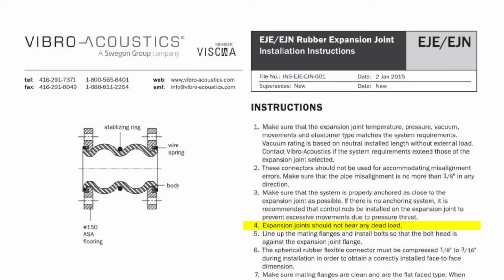Elastomeric expansion joints should not support dead loads or pipe weight. They need to be supported on either side to allow them to provide flexibility. This is a common one that is overlooked. The bolt heads should be placed against the expansion joint flanges so that they stick out away from the center of the joint. The nuts should be on the pipe flange side. I'll explain more when we get to the pictures.